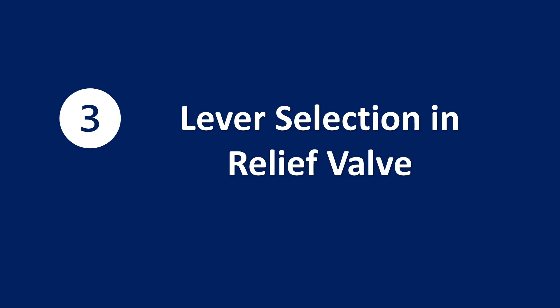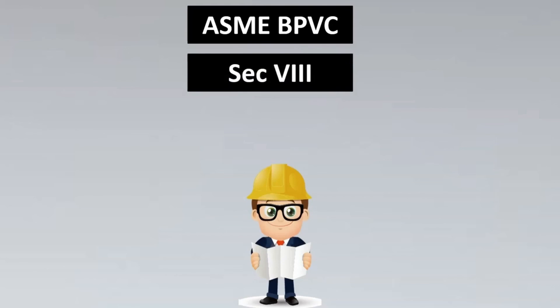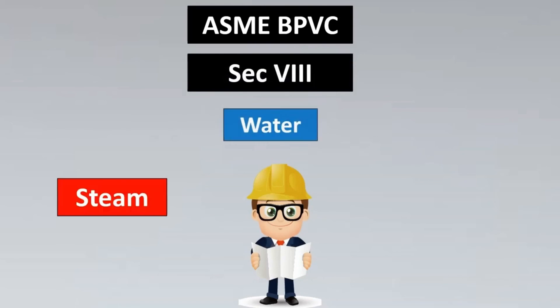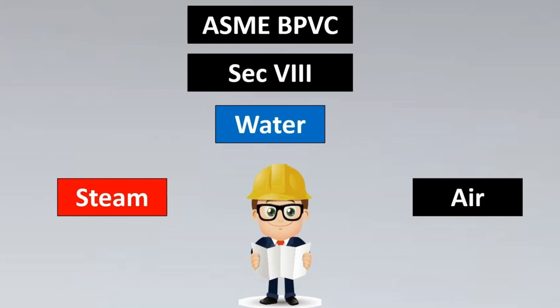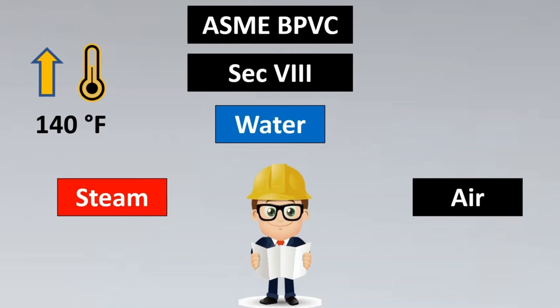Regarding which services require a lever, per the ASME international standard — specifically Section 8 — for services involving steam, water, or air at temperatures greater than 140 degrees Fahrenheit or 60 degrees Celsius, a lever should be provided with the relief valve.